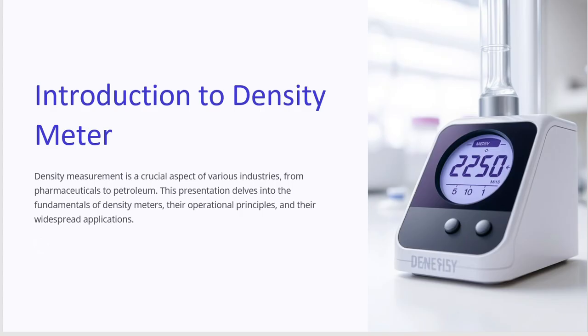As I have written here, what is a density meter? A density meter is a critical aspect of various industries, from pharmaceutical to petroleum. In short and in layman's words, we can say that a density meter is an instrument designed to measure the density of liquids or gases. Simply put, it quantifies how much mass is contained in a given volume. Most density meters operate on advanced principles such as oscillation frequency or the vibrating tube method, which are based on the relationship between density and vibration frequency.